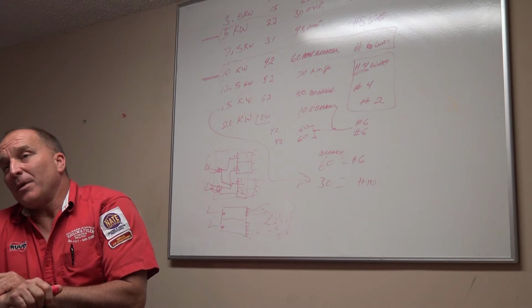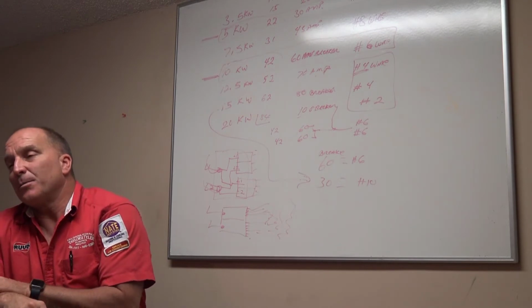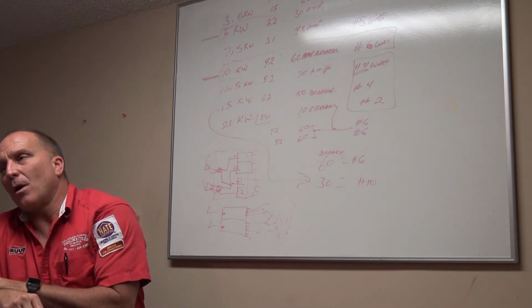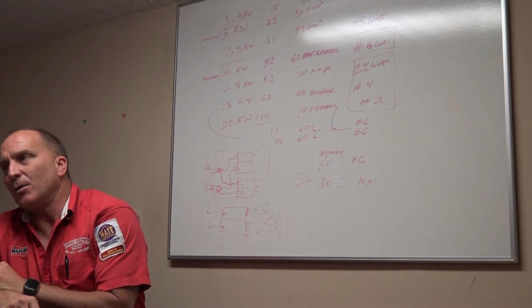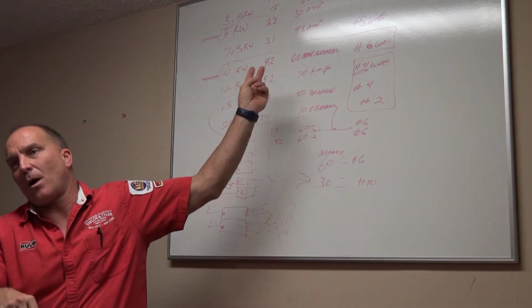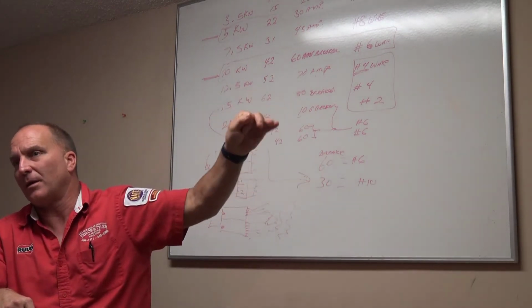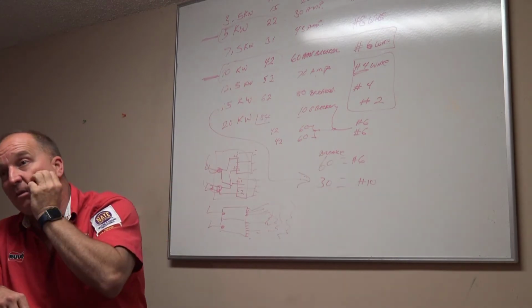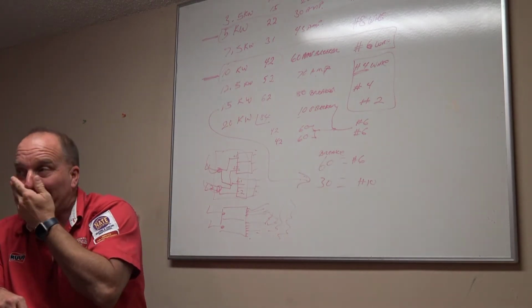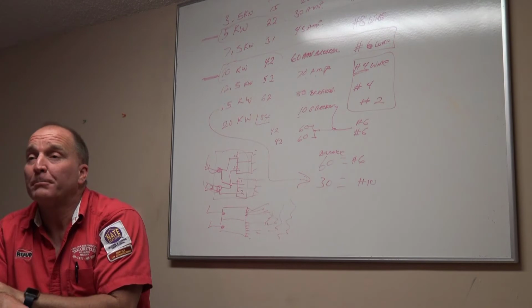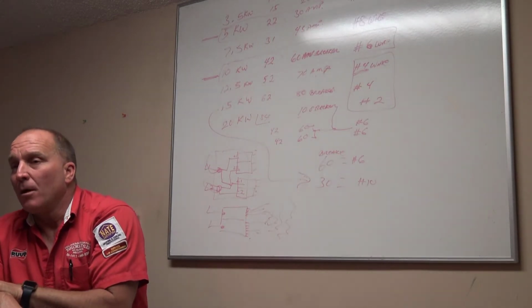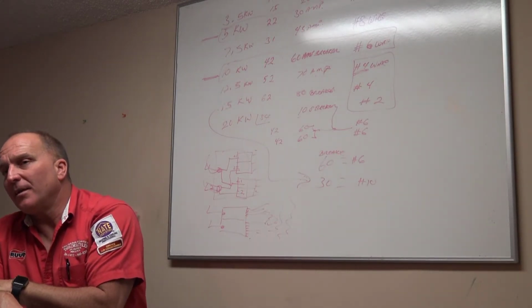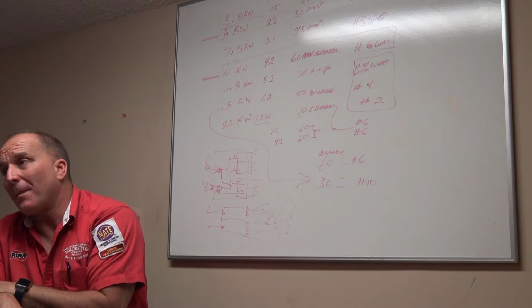What if 10 kW heat is not enough heat for this specific house, and then later on we want to add 5 kW heat to it? Okay, all we got to do is run a number 10 wire over to it and then feed that extra breaker, take the tape off of it, put it back on, now I got 15 kW heat. Okay? What if the 10 kW heat doesn't warm my home enough?